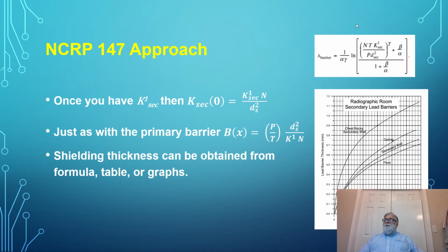We had this formula where the Archer equation is fitted with these parameters. We can go use the same tables to look up the value of the barrier that's required there. There is no X pre for scatter, no attenuation before the barrier for scatter, because it's by definition not toward the primary beam. There are graphs we can look up, again, just as we did before.